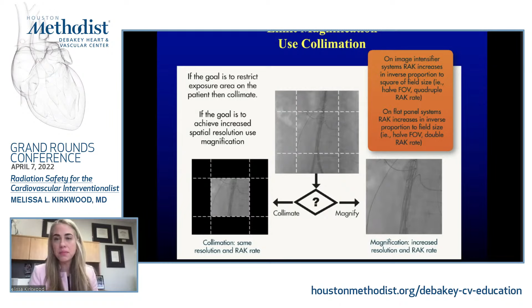So we were having to use magnification a lot to do some of these complex FEVARs, and we were wondering if there was a better way. So we looked into this new technique, which is dual fluoroscopy with live image digital zoom. And we wanted to see whether we could decrease the overall dose with this technique as opposed to your magnification. So on a Philips system, when you look at the regular magnification buttons, image zooming using standard electronic mag is achieved by changing the detector field size, which results in increased radiation dose. But if you go to the zoom control panel, you can adjust the processed image and make it much bigger on a scale of 1 to 5.